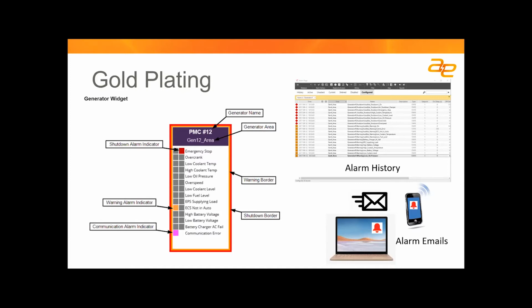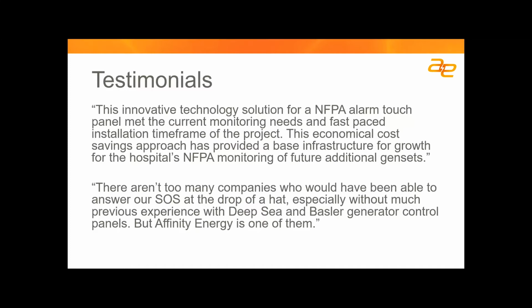Moving on, we've been deploying these solutions within the Southeast at hospitals. One takeaway is that it isn't just about the panel. The panel is a good solution, but you have to work closely with the local service provider for the generators, because they typically support the functional verification and testing that needs to occur. Whenever we implement these, we have to do point-to-point checkouts on all the alarms and all the points to make sure it works properly, because the hospital can't afford errors—they need to know those alarms will show up, and show up properly.